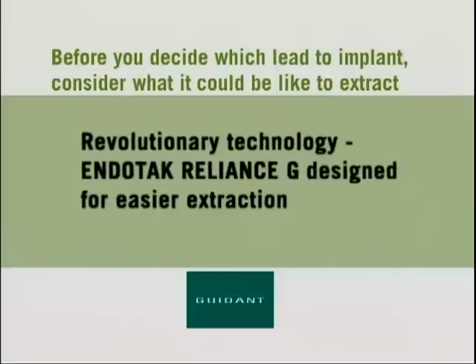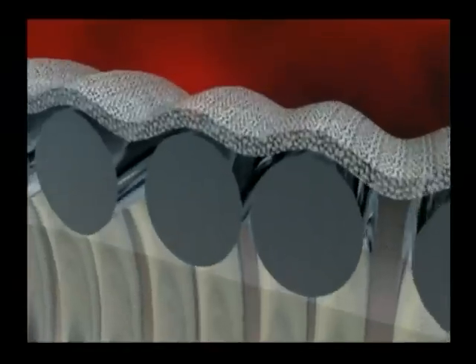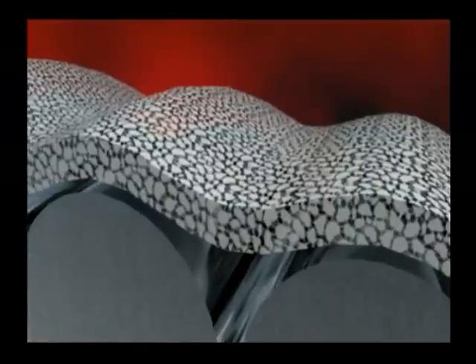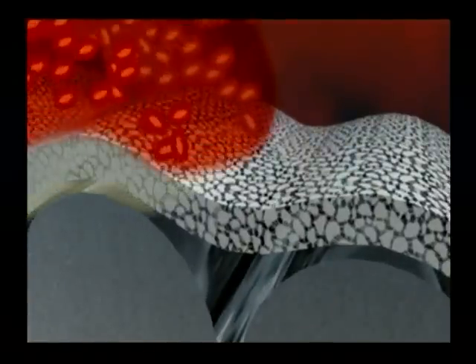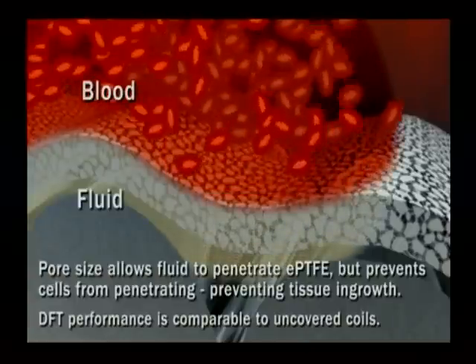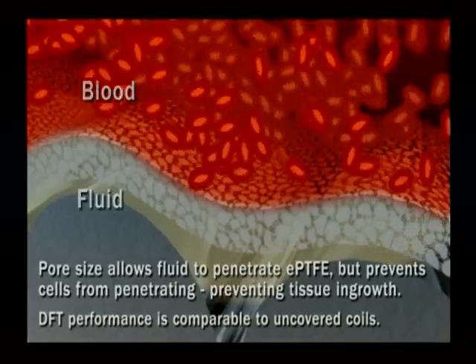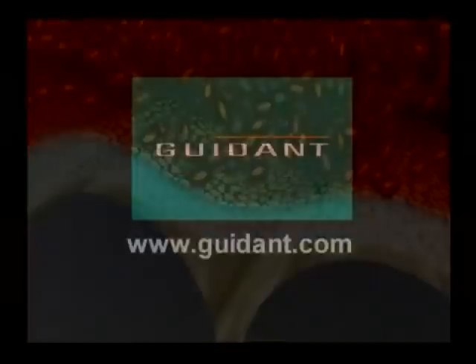Guidant's exclusive ENDOTAK RELIANCE G defibrillation lead is designed for easier extraction through the prevention of tissue ingrowth. As this microscopic view illustrates, the Gore ePTFE covering on the defibrillator coils allows fluid to pass through but prohibits blood cells from penetrating. This prevents tissue ingrowth, one of the complicating factors in lead extraction. Contact your Guidant representative or visit www.guidant.com to learn more about this revolutionary technology.